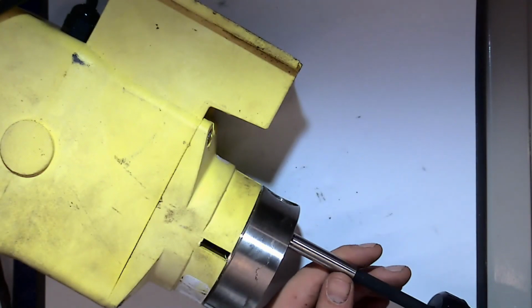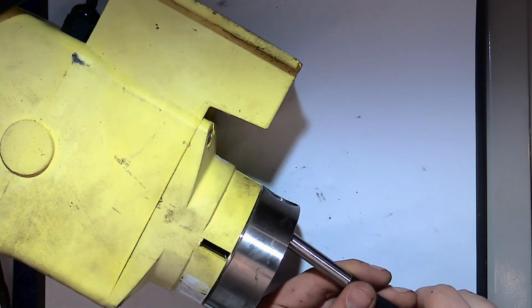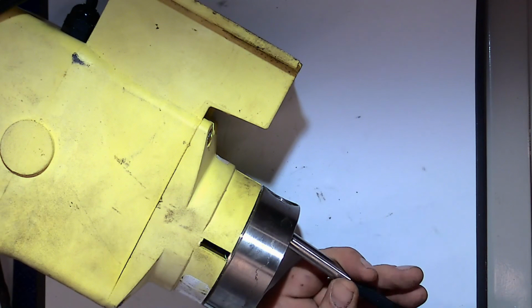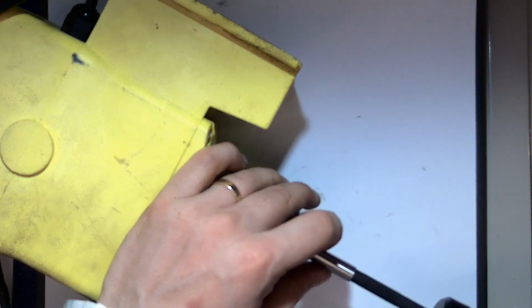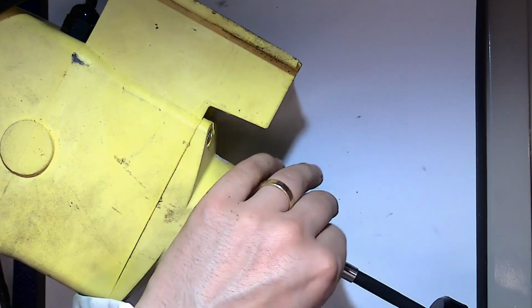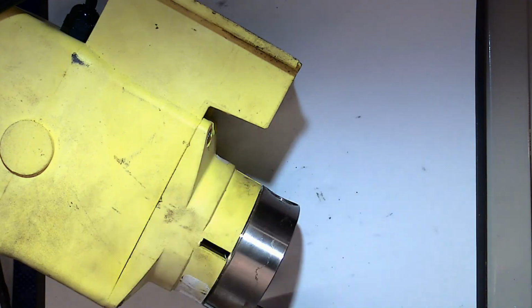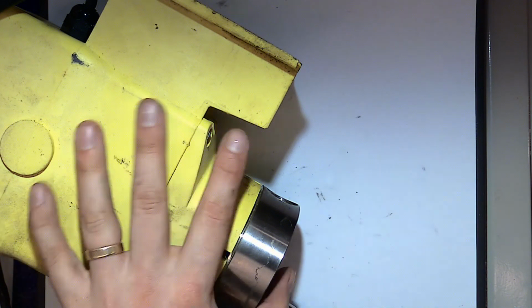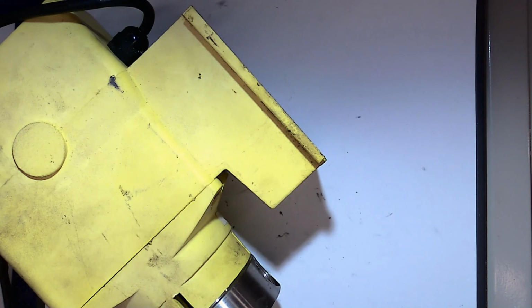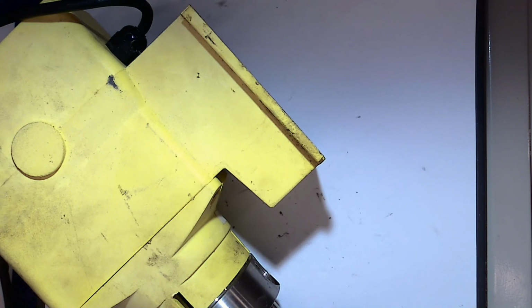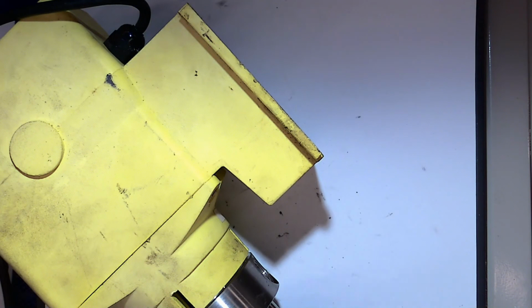Yeah, these pumps are generally used for things like dosing chlorine into swimming pools. Very similar to that. There's a control panel on the other side, and that will allow the user to decide how often, how quickly it's pumping. Whereas the other, the centrifuge pumps are far more likely to be either on or off. Yeah, so if you're having a constant flow of liquid, then you're probably going to use a centrifuge. If you're dosing chemicals into a system, you're probably going to be using a diaphragm.